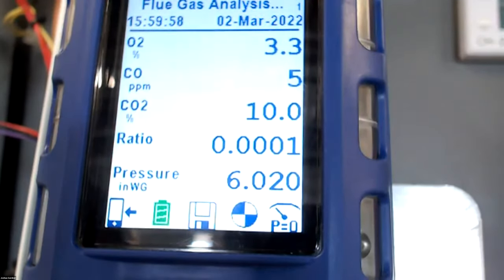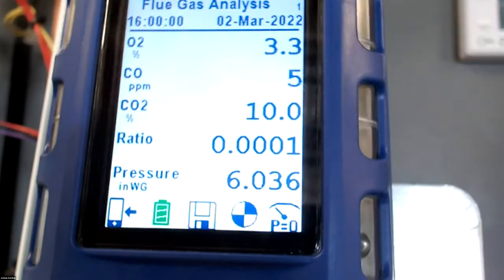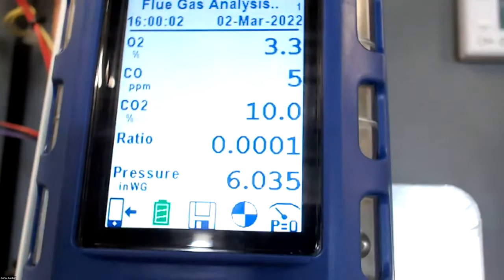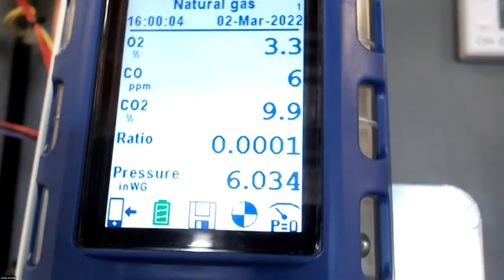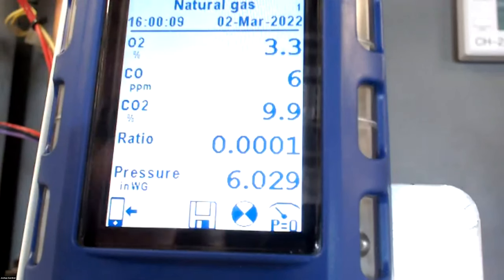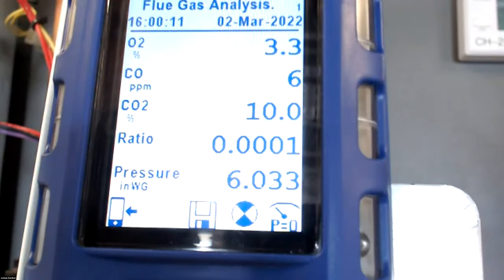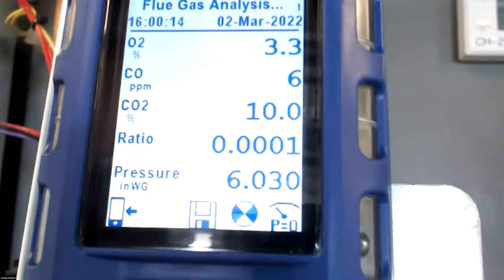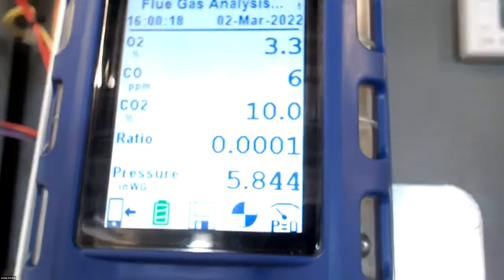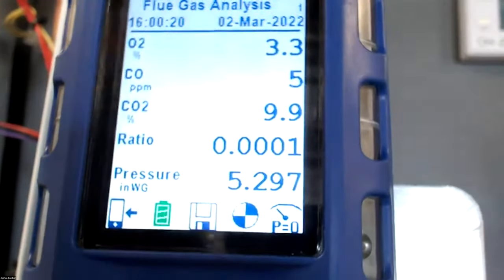So this is natural gas, a little bit different. I can't 100% recreate it, but let's say the O2 again is running at 6 and we're running way too lean. We adjust that gas pressure. I'm just going to shut this off, because I'm going to show you guys on this. What I'm going to do is remove this cap, and I'm going to remove this 90, this outlet 90 right here.